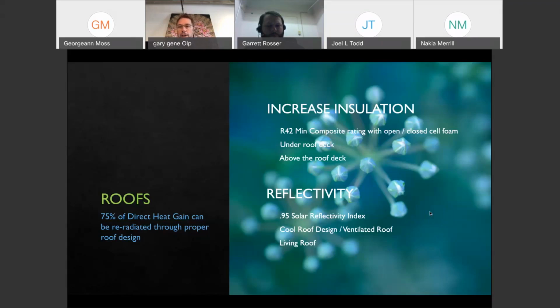Cool roof design is where you ventilate the roof. Imagine an umbrella, if you could put an umbrella over your building, or as you see a lot of folks do in the South, carry an umbrella out in the sun. That umbrella, if you will, really can cool down your roof. Trees are a good source of that, but the problem is when you get them too close to the building, you can have issues with the roof. The other problem is trees drop their leaves, and unless you have regular maintenance, it can be problematic. So there's trade-offs to all of this, but a simple thing to do is raise the roof membrane about 1 inch off the deck, and then ventilate that so air can move under it. You create a thermal siphon, and air moves under that roof, pulling heat out and away from the interior, and that's how you can get to 95%.